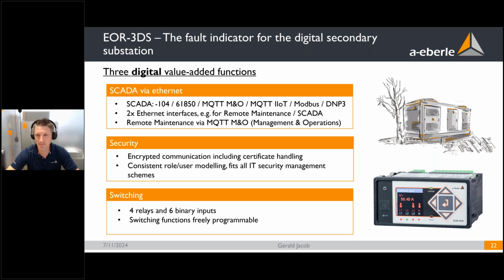For the switching application, the device has 4 monostable relays on board and 6 binary inputs for getting information from the earthing switch and the load breaking switch. Similar to our regulators, RegD and RegDP, which have background program possibilities meaning a PLC functionality, our EOR3DS has the same possibility. So you can also equip the device with customer-specific applications, like switching.